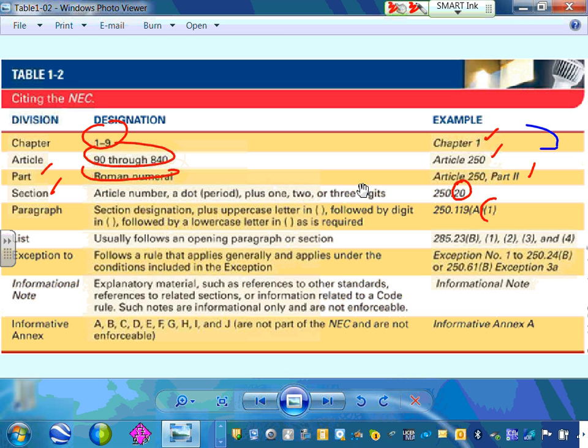So they put a '1,' and look—they put an 'a' and a '1' after that, and it becomes a whole paragraph or list. We have list two, here's list 1, 2, 3 items under B. And we have exceptions—the code book loves exceptions. They'll tell you a rule, like all receptacles in a basement must be GFCI, and right underneath they say 'exception: a single receptacle dedicated for a fire alarm or burglary alarm system.' So if you have one receptacle in your unfinished basement dedicated to a fire alarm or burglary alarm system, it doesn't have to be GFCI.